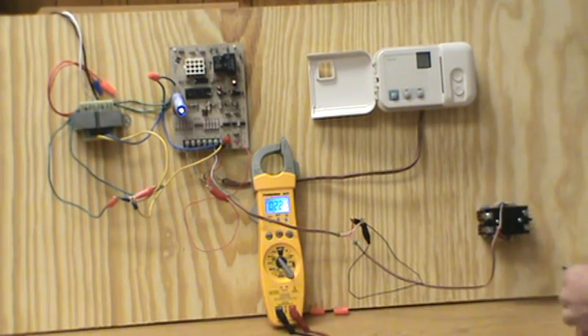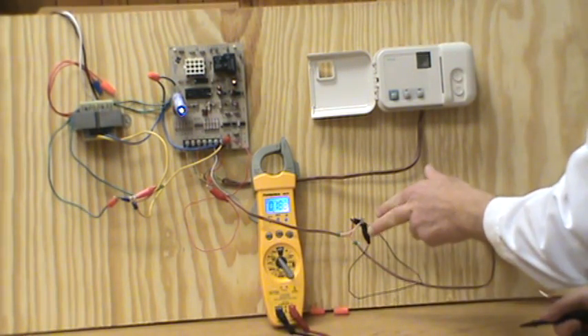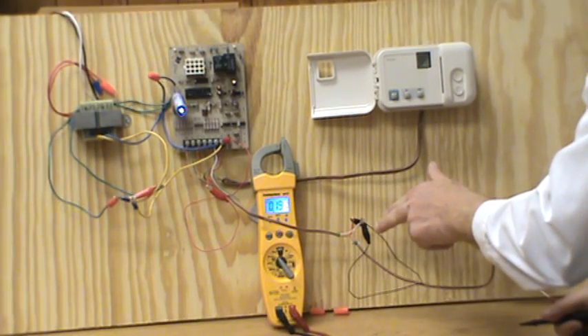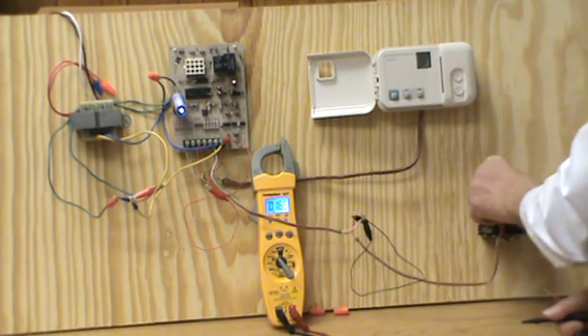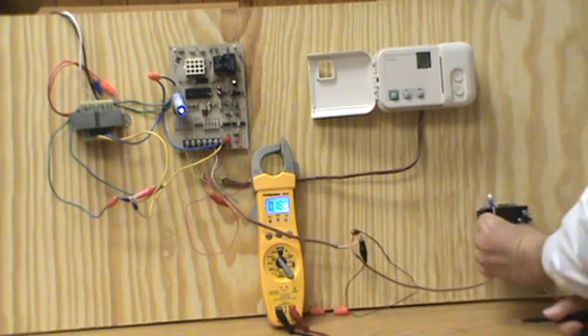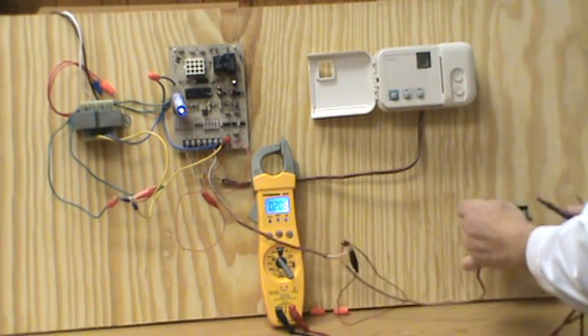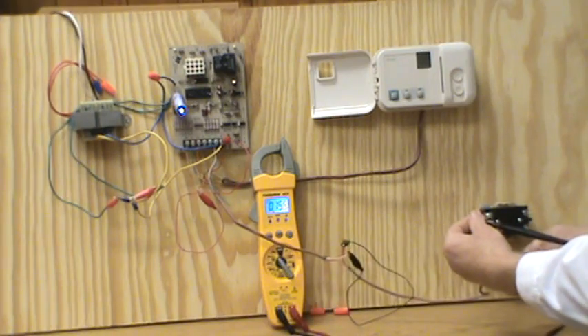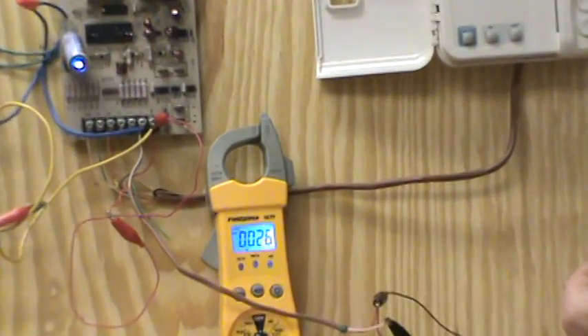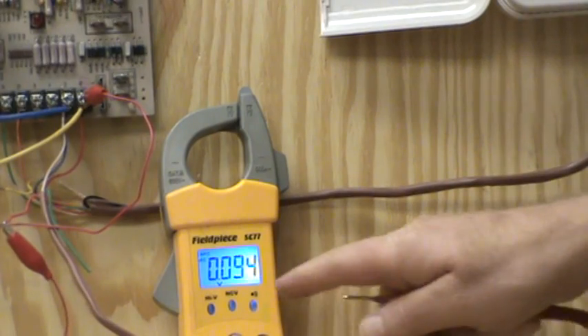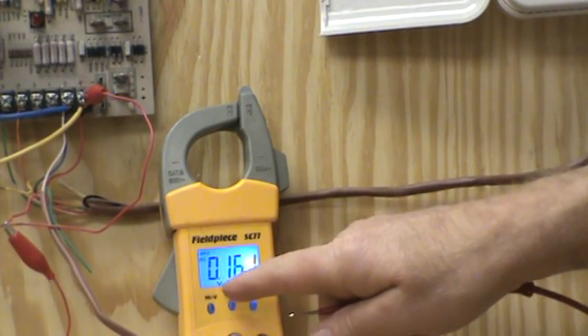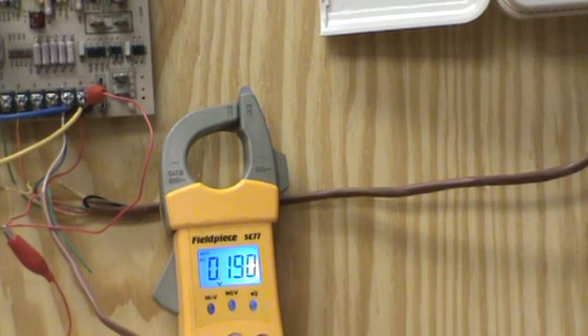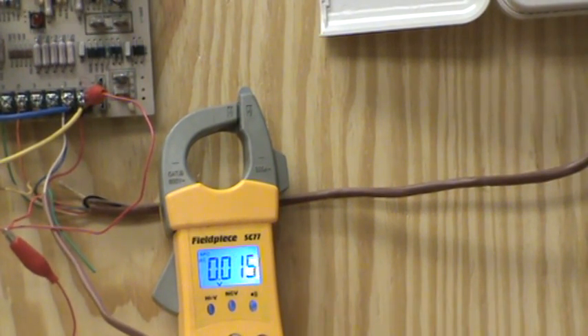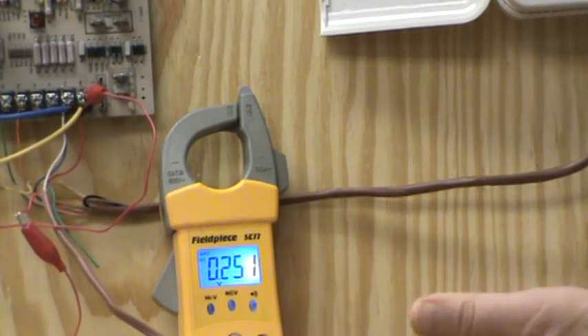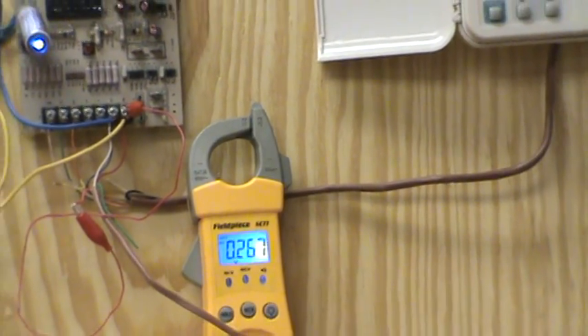And check voltage. Now, we know that we've got the short somewhere in the wiring up in the attic, and all you got to do is take apart the power wires going through the condensing unit and check voltage. Now in this case, I've got no voltage. The 24 volts would have been on this side. We got 0 point, and it gives a few odd numbers because it's a digital meter, but there is no voltage at the condenser. That is because the short is in the attic going out to the unit outside.